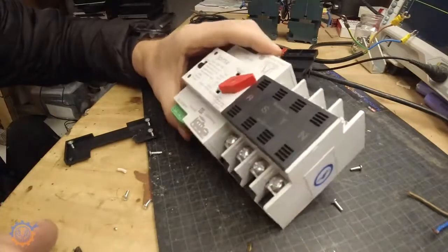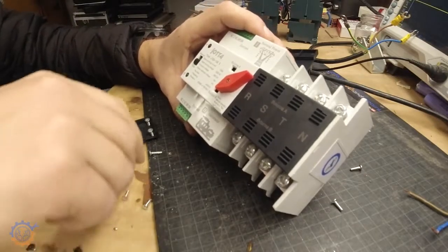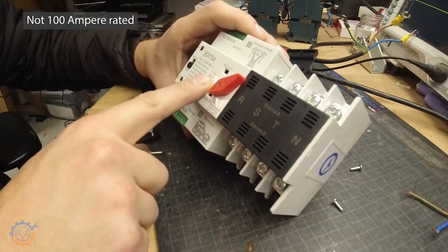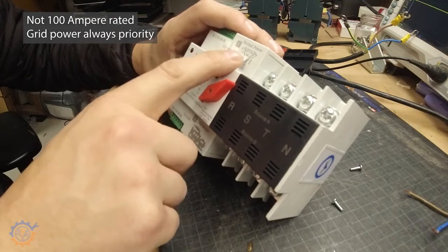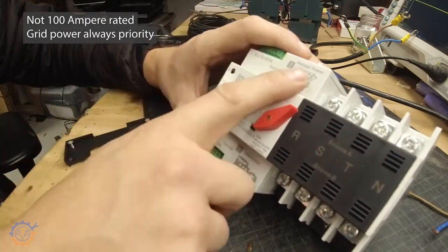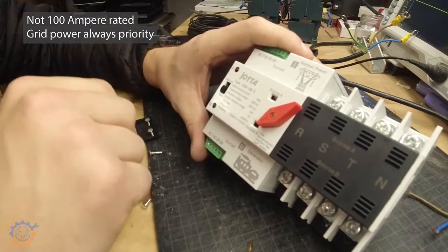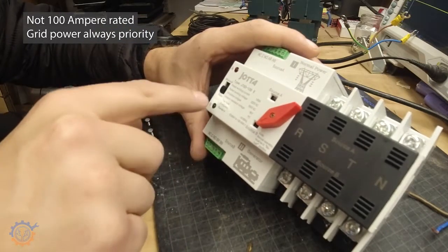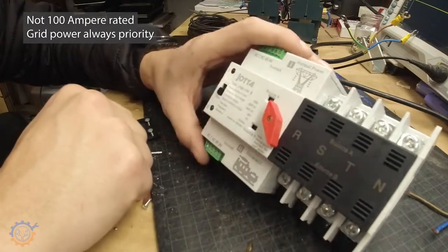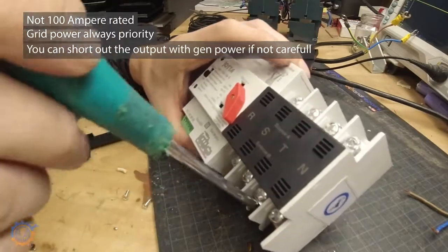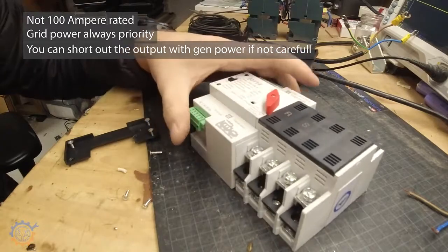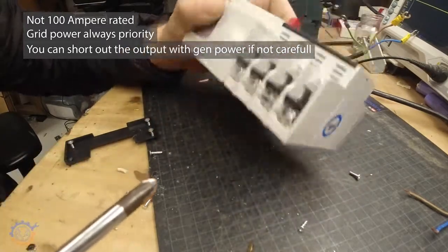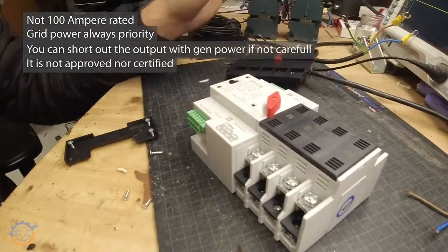So final thoughts about this device. First of all 100 ampere is not accurate. That is way too much. Secondly it only handles normal power as the primary power. You need an extra relay and a switch to actually be able to switch between those two live. Otherwise you need to go to manual and strike this one like that. Thirdly the contacts here are way too close to each other. You can short them up as you can see there. That is a big no-no as well. And the fact that this one may not be approved. That is also a big disadvantage.